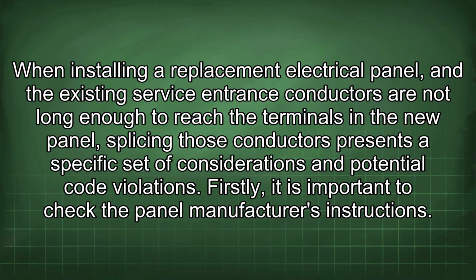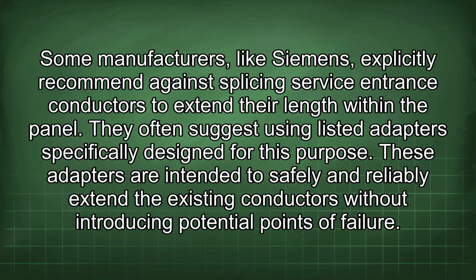When installing a replacement electrical panel and the existing service entrance conductors are not long enough to reach the terminals in the new panel, splicing those conductors presents a specific set of considerations and potential code violations. Firstly, it is important to check the panel manufacturer's instructions. Some manufacturers, like Siemens, explicitly recommend against splicing service entrance conductors to extend their length within the panel. They often suggest using listed adapters specifically designed for this purpose. These adapters are intended to safely and reliably extend the existing conductors without introducing potential points of failure.